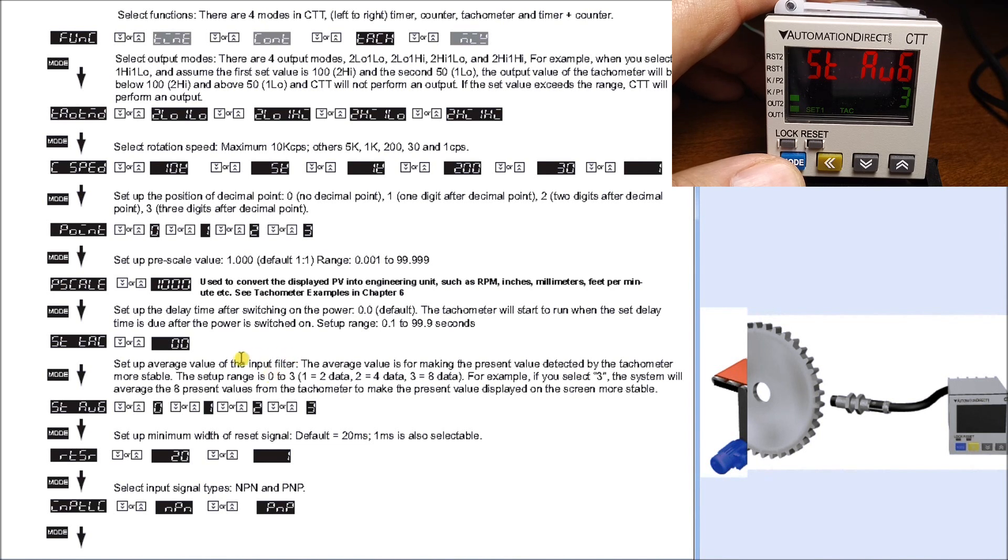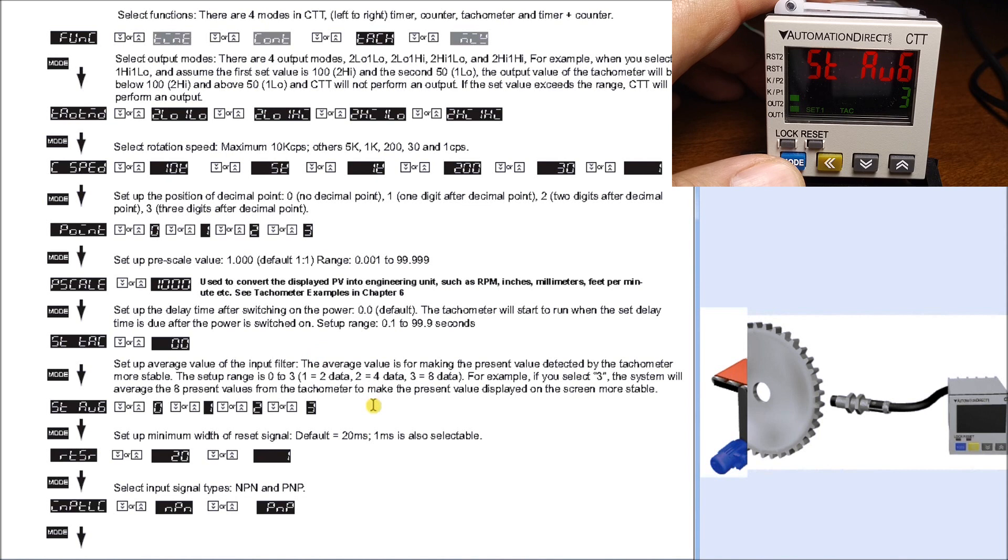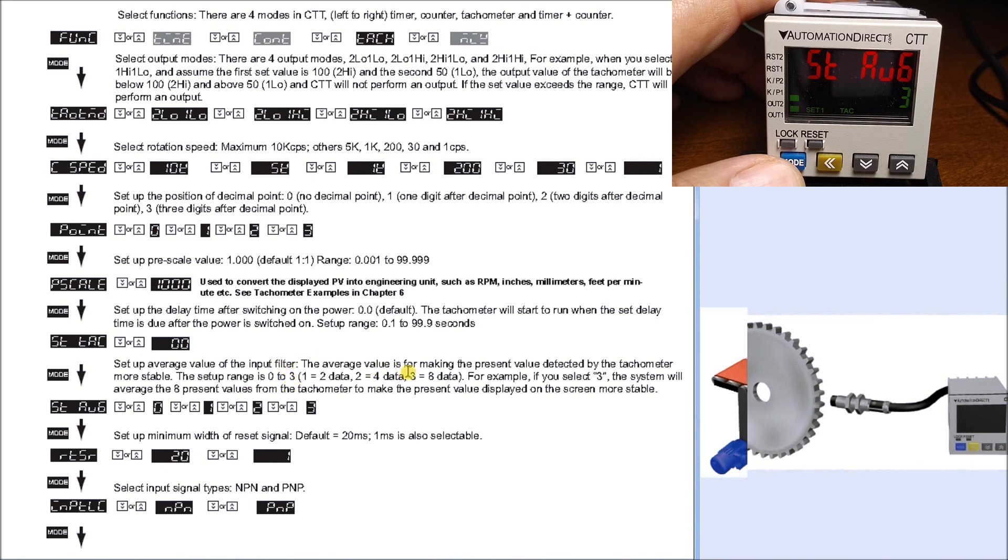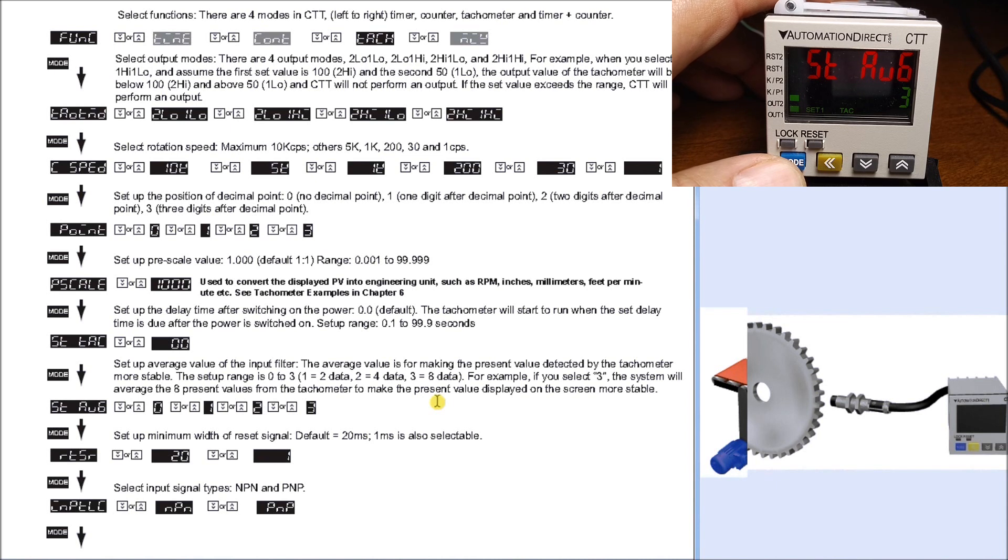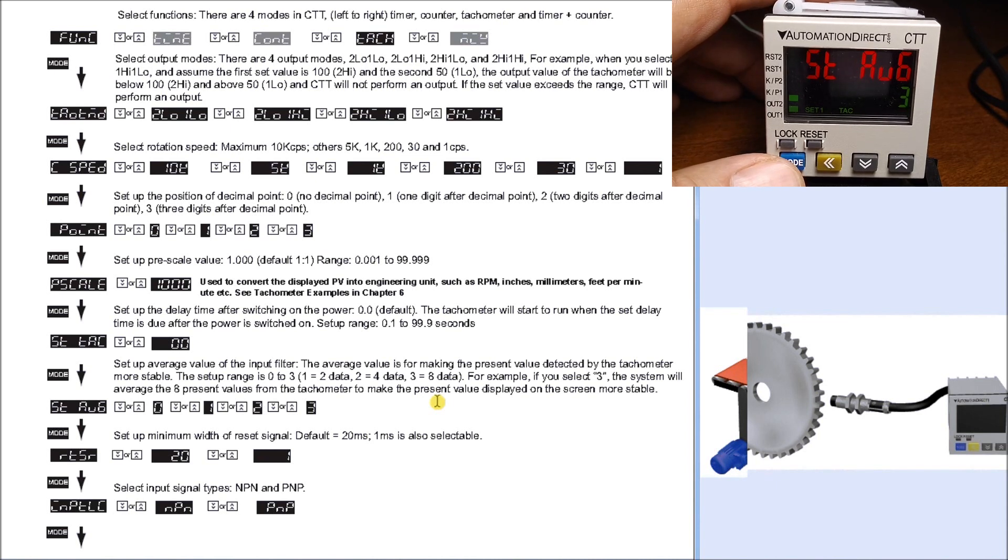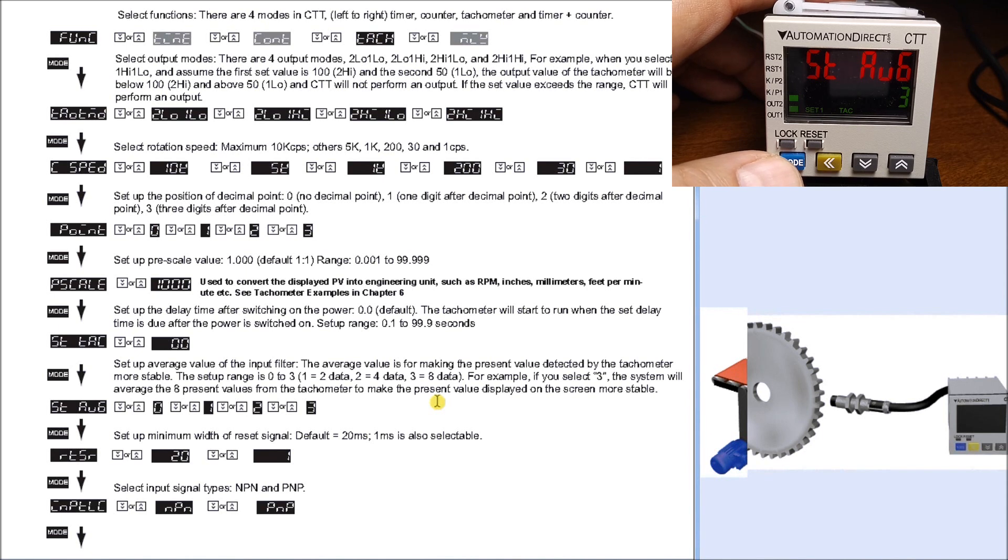This sets up a filter we can place into the CTT to filter this out and make the output more stable. Our setup range is 0 to 3: zero means no filtering at all, and three means eight times - sample eight times before we give an output. In this particular case, we're going to use a value of 3. You'll have to experiment with this in your application to determine what makes sense for you and the response time of your outputs.